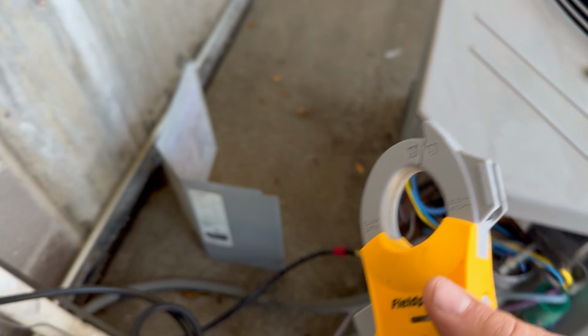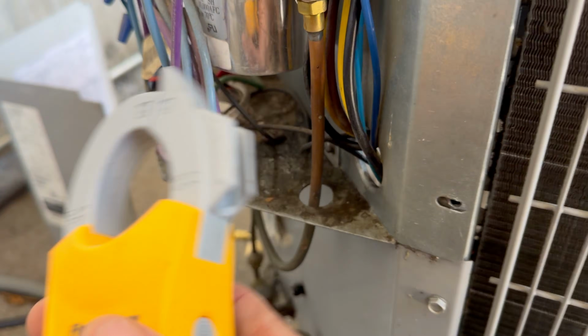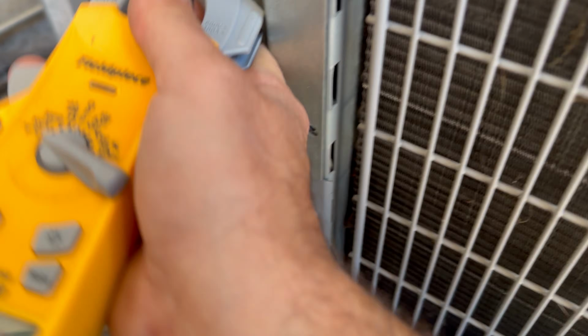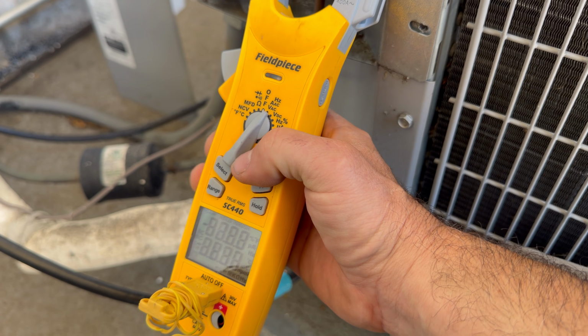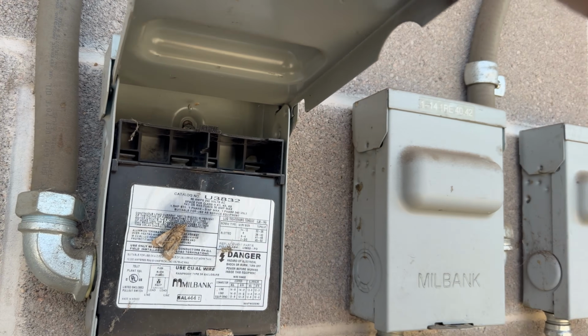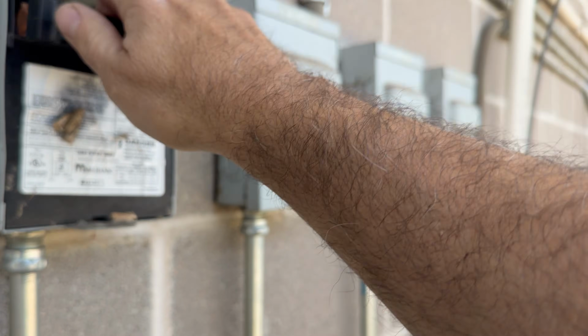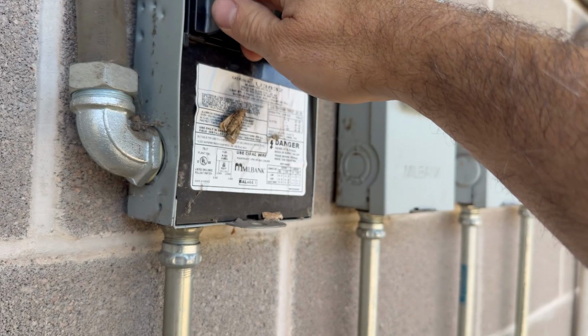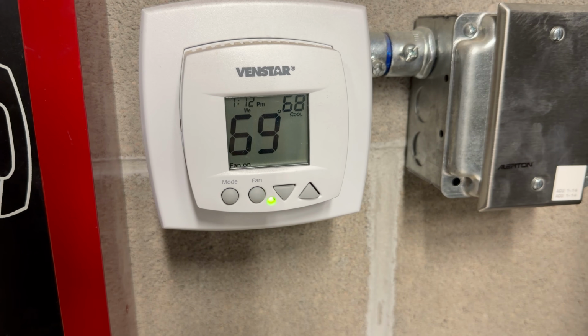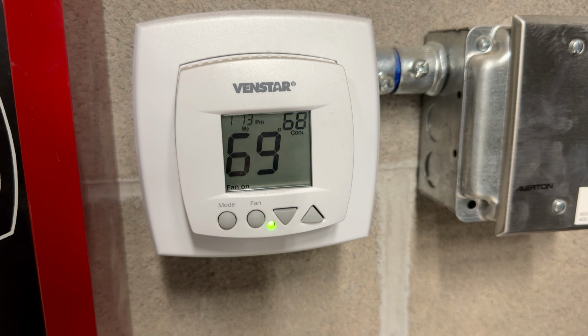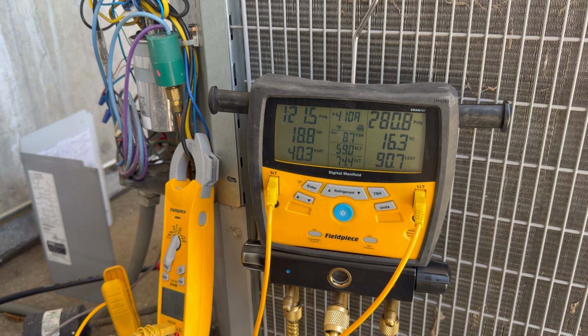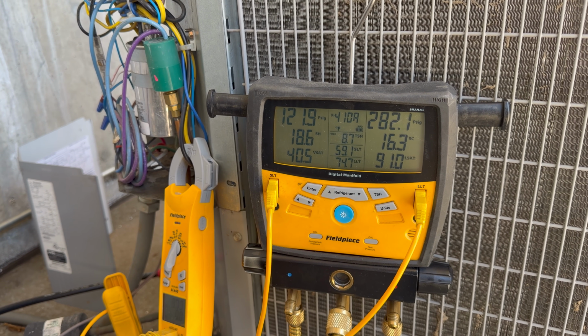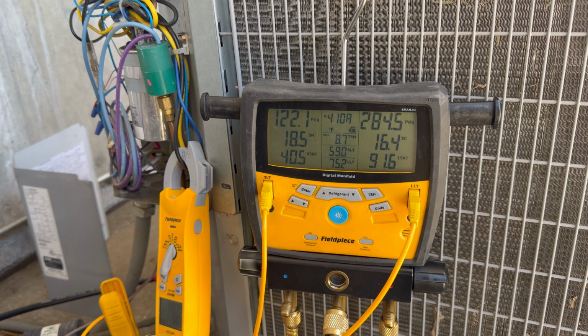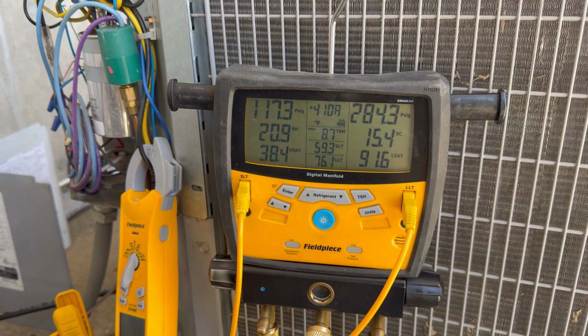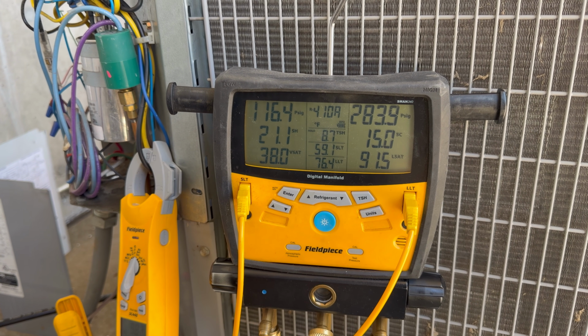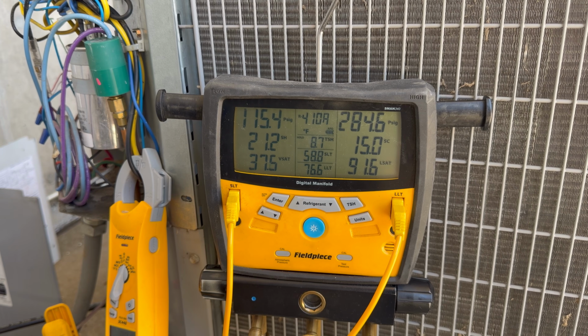77 degrees. Now we're gonna go ahead and clamp our compressor run wire. Turn the power on and monitor the heat load inside for about 10 minutes, but I wanna make sure that this coil is nice and dry or it's gonna throw our readings way off. Heat load inside just dropped 1 degree below our previous heat load. All right, head pressure, our subcooling's a little bit higher than it was, but we're not really stabilized yet. All right, as far as pressures, we're about 5 PSI lower than we were on the head pressure. Superheat's about normal for these units.